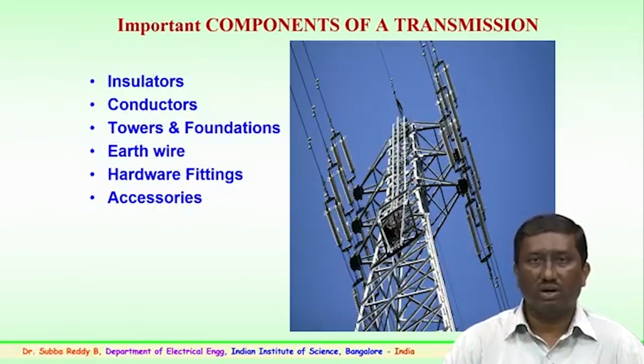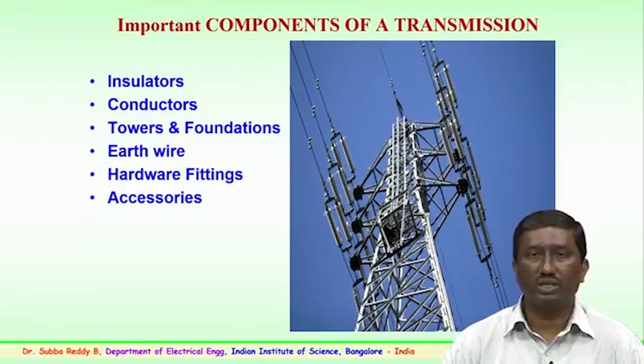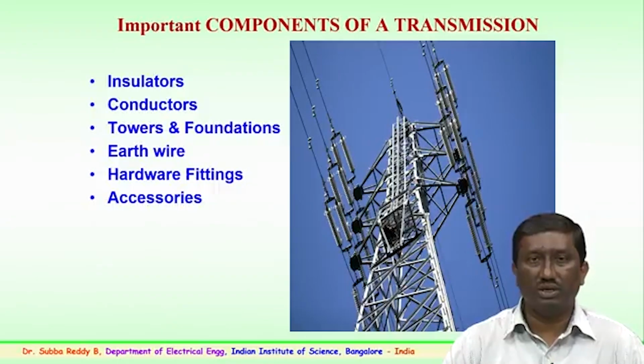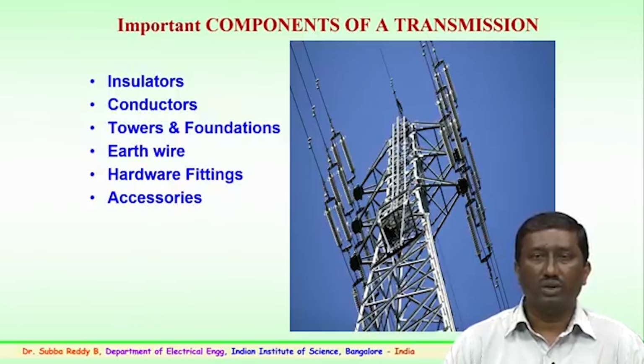Insulators are of mainly three types. Initially, for the last 100 years, we have been using ceramic or porcelain insulators. Europeans use glass insulators. Then of recent origin, polymer, composite or silicone rubber insulators are being employed for the transmission network. So, these are of recent origin. We will be looking into various types of insulators, how they came into existence, what the advancements in this insulator technology are, and what the problems related to the insulator technology are, particularly when used at extra high voltage and ultra high voltage transmission systems.